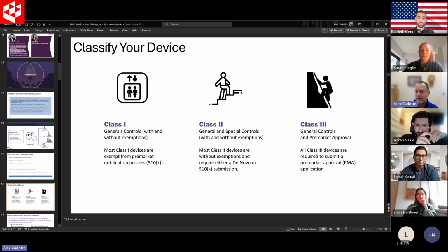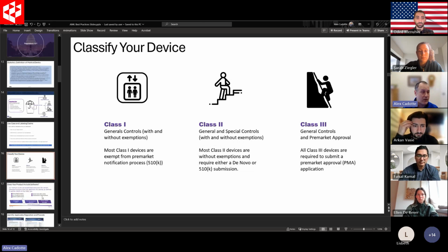Class 2, it's kind of interesting. It used to be there was a process with PMA that would have your device on the market as a Class 3 for a number of years, and then it would get down classified to Class 1 or 2. FDA decided to speed that process up with what's called a de novo. So it's basically a benefit risk submission that at the end of it, FDA classifies your device as either Class 1, Class 2, or Class 2 with special controls. Special controls are basically specific things that you have to do for your specific device, and anybody that does a 510K relative to your device has to do those things as well.